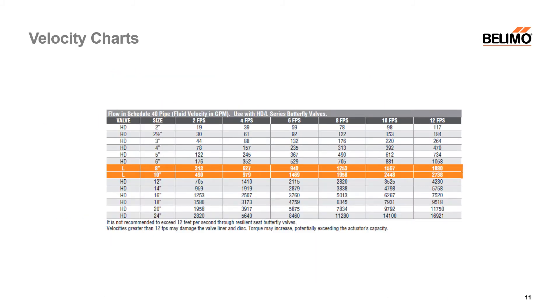Another consideration is velocity. The HD and L series valves have a 12 feet per second maximum velocity. If ordering this valve, you would take your gallons per minute, refer to the chart in our catalog, and check the maximum velocity that a given size — say a 6-inch — could handle. The Victaulic grooved series can do up to 20 feet per second, and the high-performance valves are rated up to 32 feet per second.